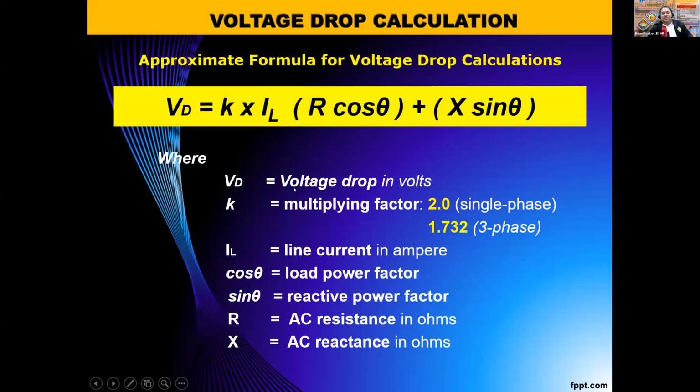Okay? Si multiplying factor is 2 kung single phase. Then square root of 3 or 1.732 sa 3 phase. So as you can see in this equation alone, mas mataas expectedly si yung voltage drop ng single phase systems compared sa 3 phase. Kaya nga mas less yung losses ni 3 phase. Ito yung advantage ni 3 phase talaga, voltage drop handling, no? So dito pa lang makita natin sino yung mas mataas. Okay?